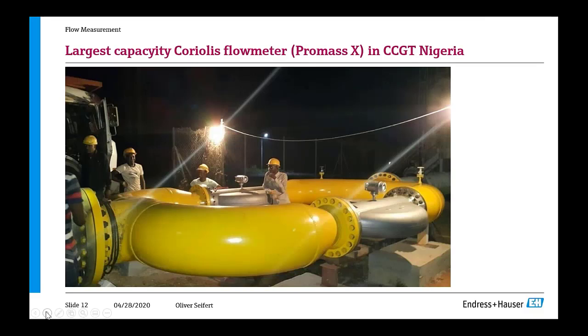Here's another reference. That's a bigger line size. Here you have two of our largest Coriolis meters, two 14-inch meters in parallel, measuring this inlet to a combined cycle power plant in Nigeria.